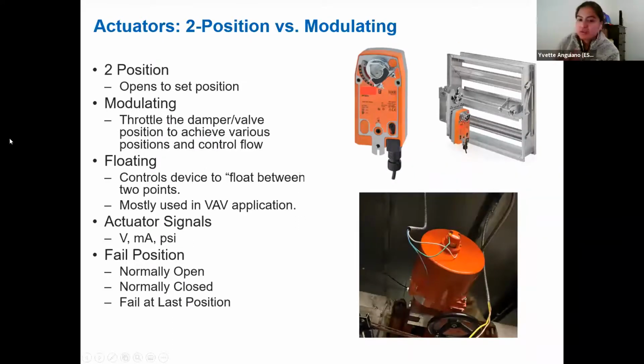Okay, so then getting into your actuators. Typically your actuators are furnished separately from your dampers and valves. So it would be up to your mechanical contractor to install that damper or valve, and the BMS contractor would then install your actuator to control the damper and valve. As stated previously, you do want to choose your dampers based on the best application for control. And you also want to have those considerations for the type of valves that you're using in a control setting, but we won't be touching on valves today.